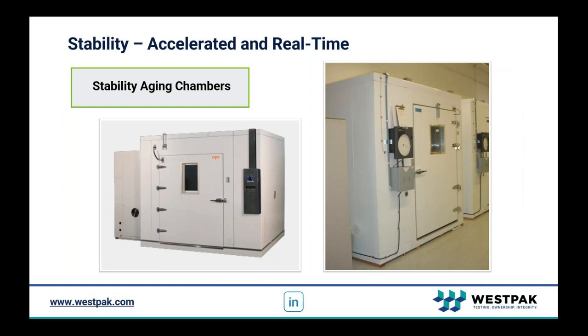And remember that you need to do real-time aging in addition to accelerated aging. It's required to validate your accelerated aging data.